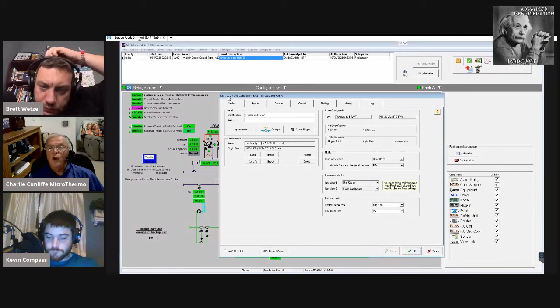Now get this, we make a motorized head that you can retrofit onto an A8 and A9. Back from my days when I was strictly a mechanical guy, I would do classes and think, wait a minute, which one do I do? Do I do the A8 first, or the A9 first? So to take all that mystery out of how you set those valves, you put a motor on the A8 and A9, and then you use the 2-valve controller to feather. One is a holdback valve and one is the receiver controller, just to control the receiver in a standard system.